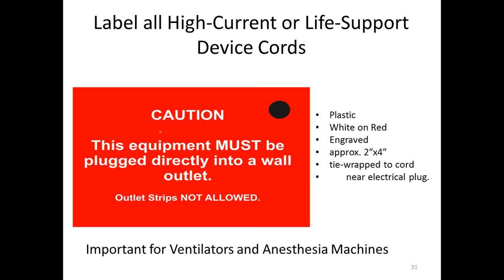This is an example of an engraved sign that we had made, and they're probably still all over the hospital. They're made of plastic and engraved, and we tie-wrapped them to the electrical cord near the power plug. It instructed users that this unit has to be plugged into a wall outlet and was not allowed to be plugged into an outlet strip. We used this for ventilators, anesthesia machines, lasers, and ESUs. We would not allow those units to be used on a multiple outlet strip and required them to go straight to the wall.